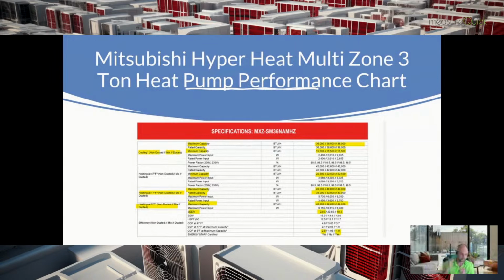And for that zone, it's going to modulate at that same temperature. Basically, the same thing is turning on and off at that same exact BTU output, and you might end up getting moisture problems over there, or you might end up not getting any kind of cooling turn down at all to service the part load conditions, which is what you're trying to achieve with these things. So you have to be aware of that.